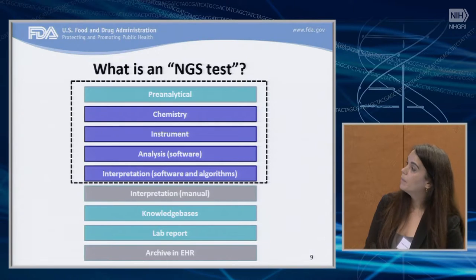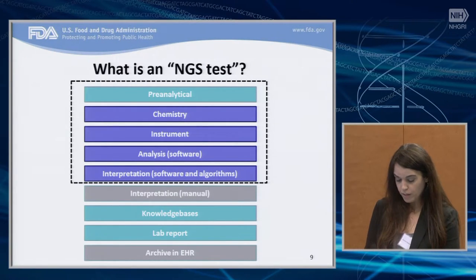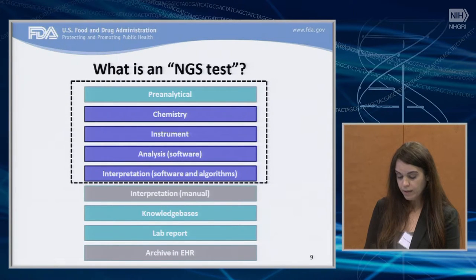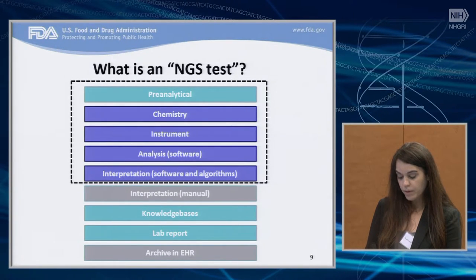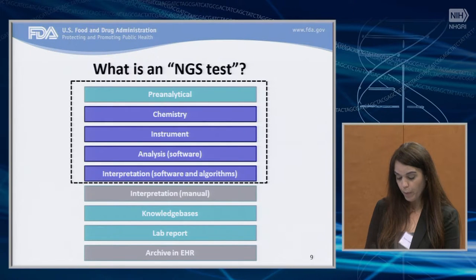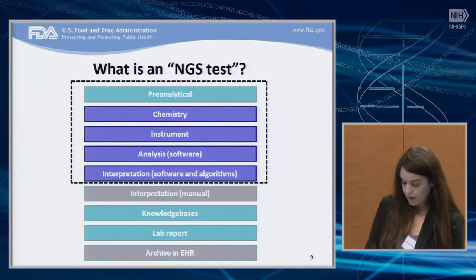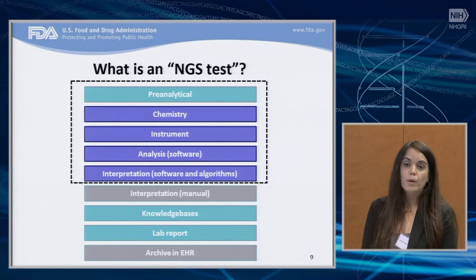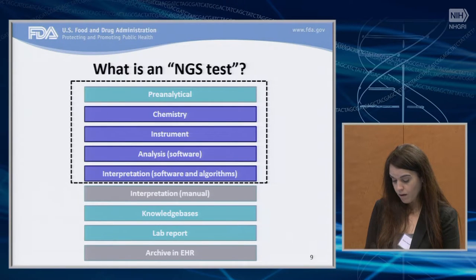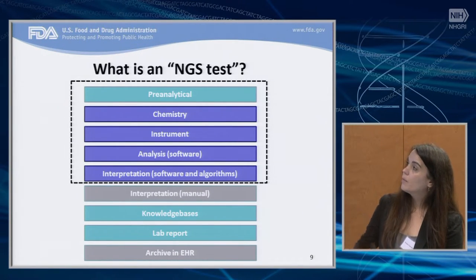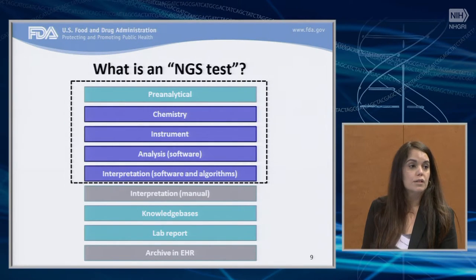We want to give you an idea of what we would consider the device in terms of next-generation sequencing. This slide illustrates the different components that could comprise the test, including the instrumentation, reagents, software, and databases. The device is all of the components that will take a specimen — whether it is DNA, whole blood, saliva, urine, or any other sample type — and transforms it into a result that will be included in the lab report. The area boxed in on this illustration is what we would consider the device, and what we would be looking for information on, either in a pre-submission or in an IDE, in terms of analytical validation.